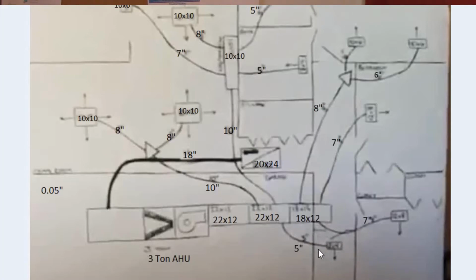Well, guess what? There's nothing that's free. Nothing is free, not even air. So we have to take that into account. This 5-inch right here is stealing air from this whole system. We have to account for that. So anyway, given all of that, this 10-inch right here is going to give us 300 CFM at best if it's only at 4% compression, considering it's not snaked around anything. If there is any snaking here, if it's being bent in any way, shape, or form, and it is not a short, straight run, we are going to get somewhere between 120 and 175 CFM through this run.